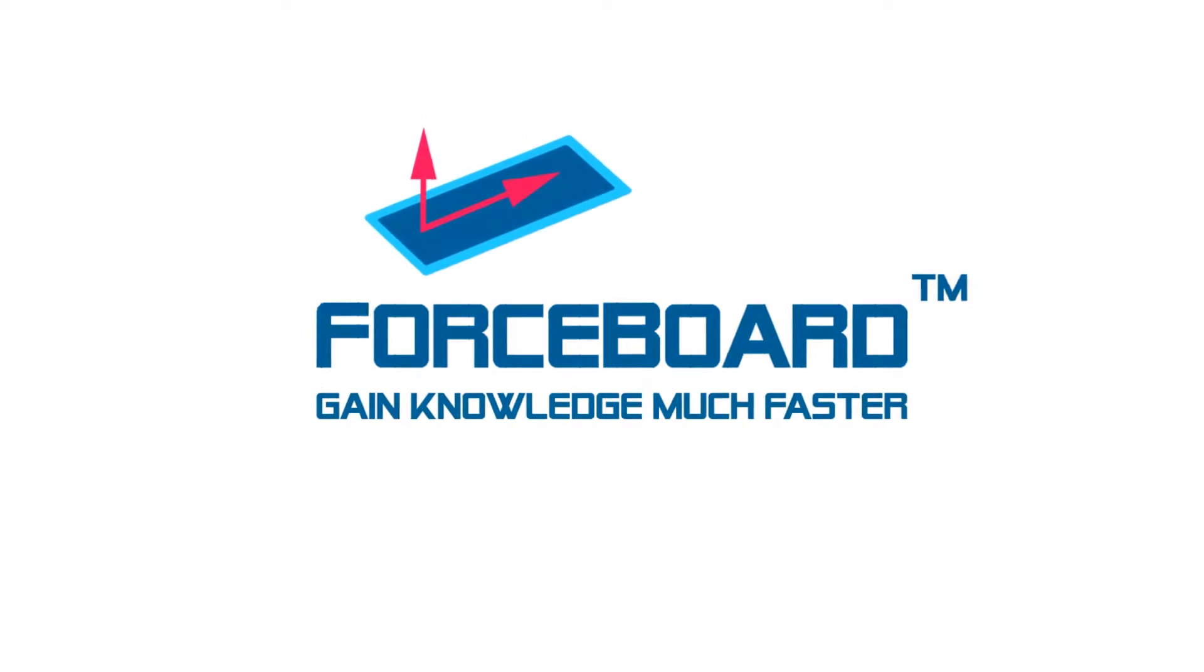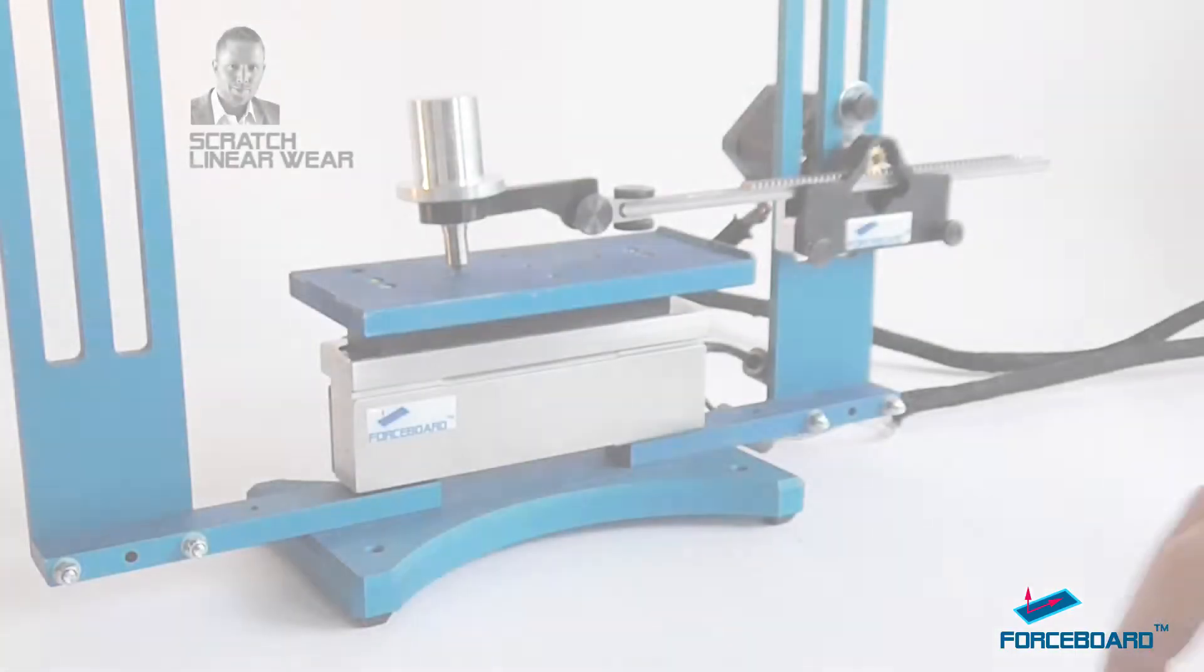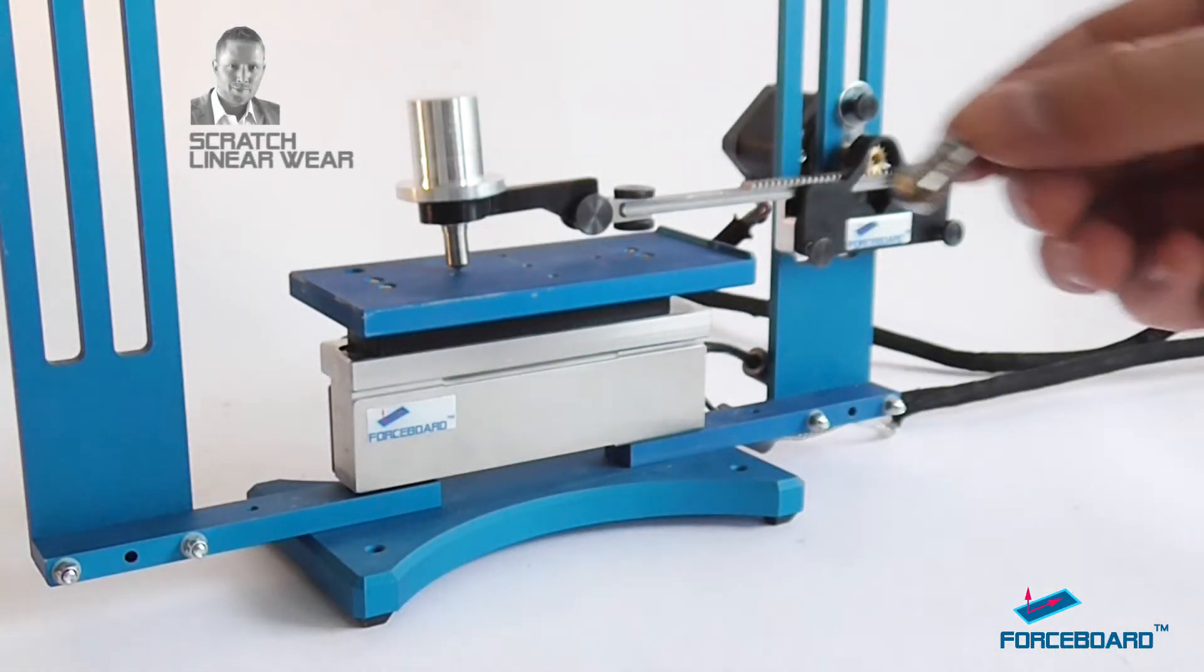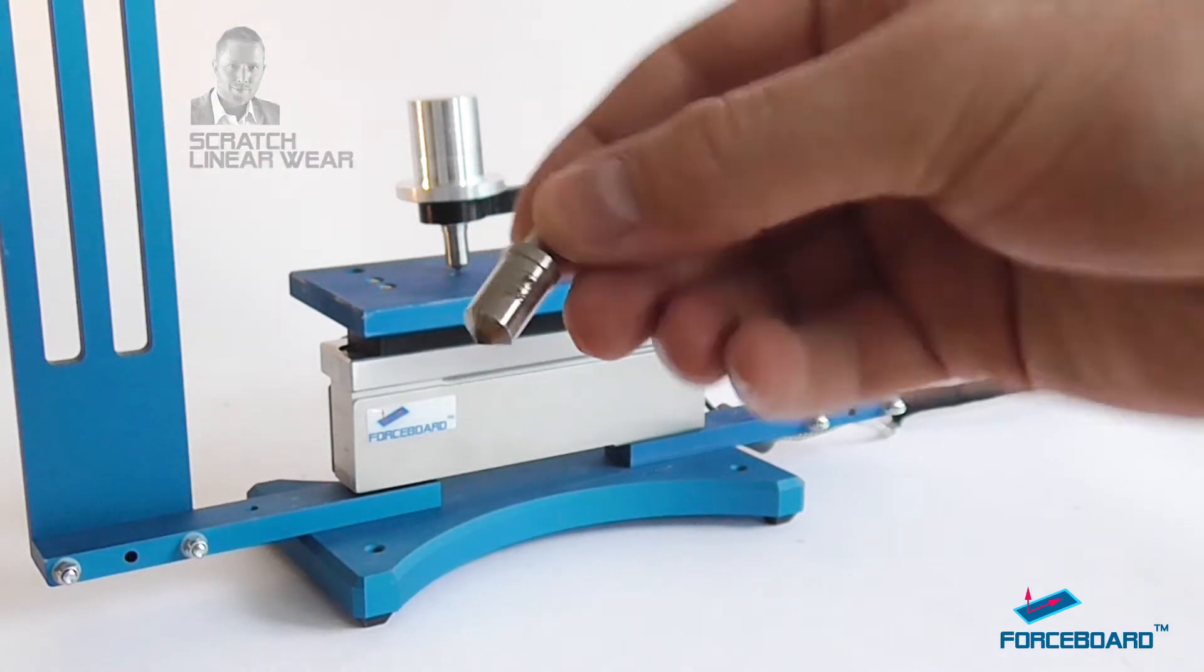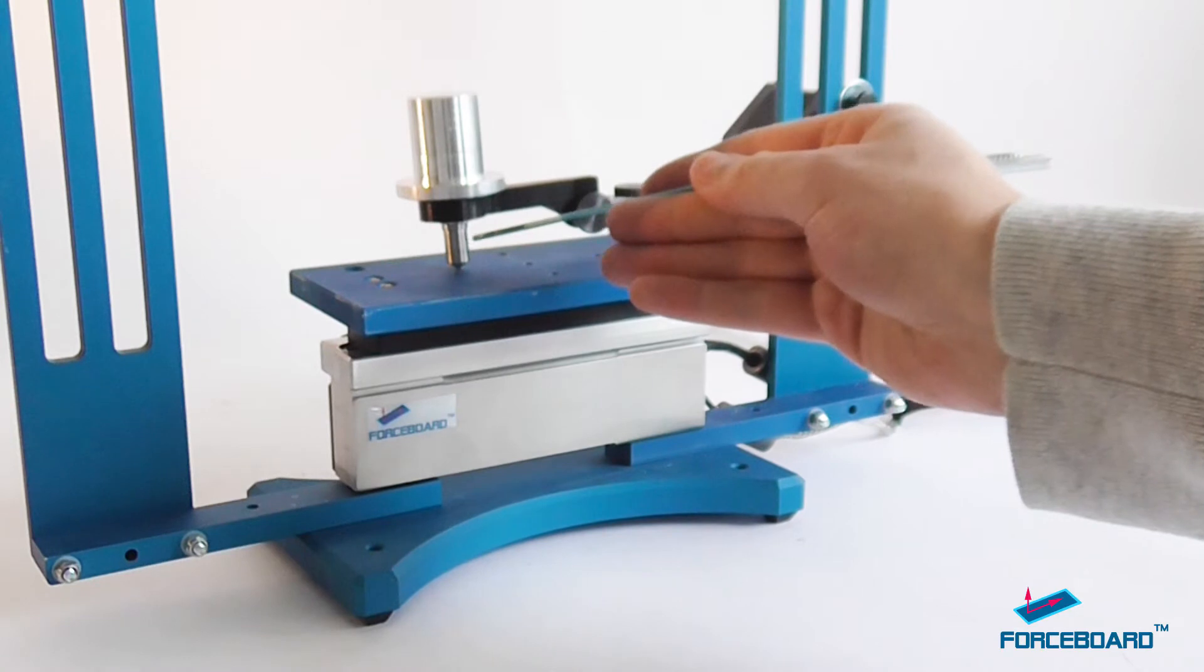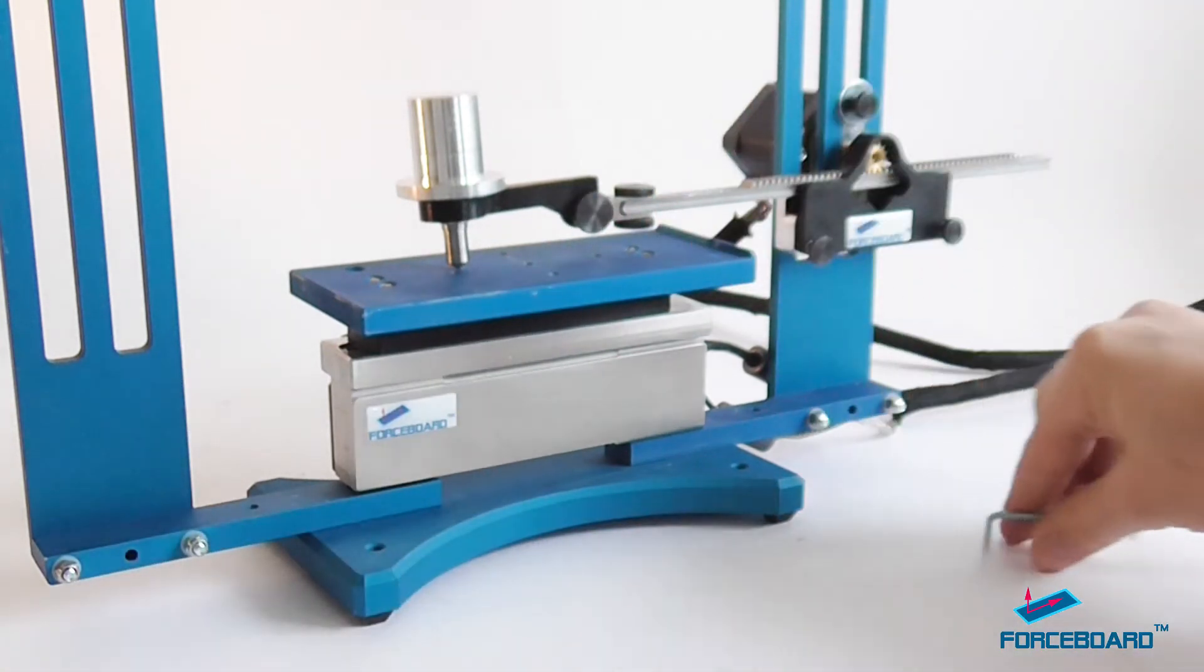My name is Marcus and I'm the founder of Force Board. Now we're going to talk about scratch and linear wear testing. In this test we will be using a Rockwell industrial grade diamond probe with a 200 micrometer tip radius.